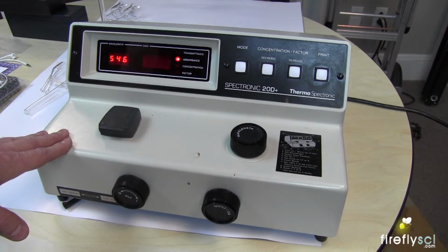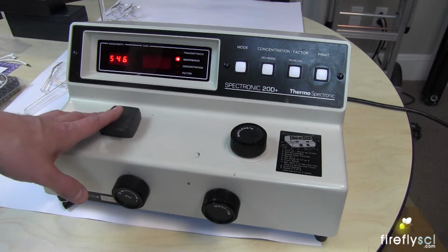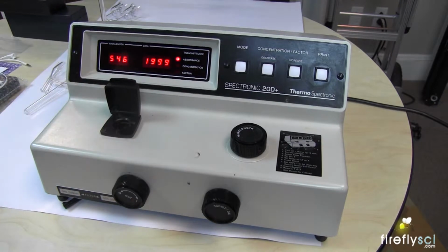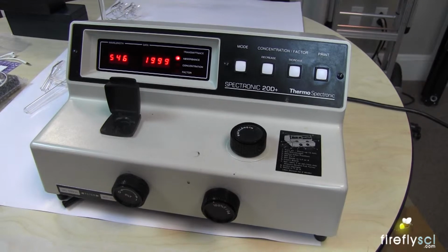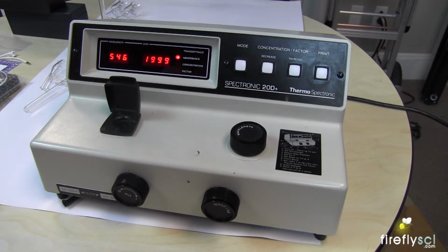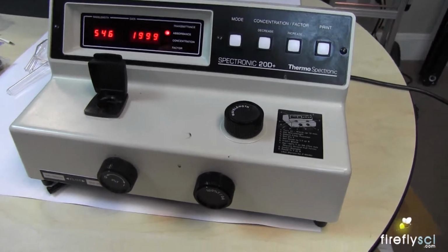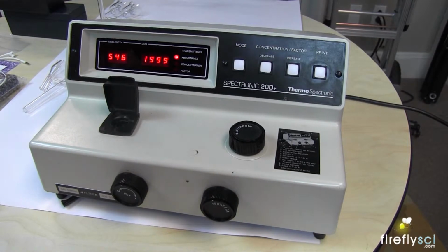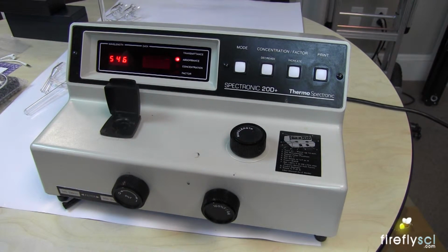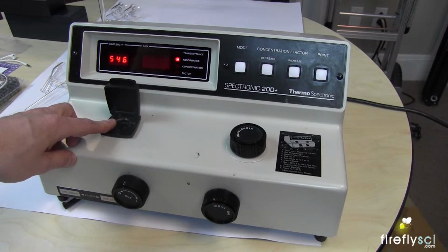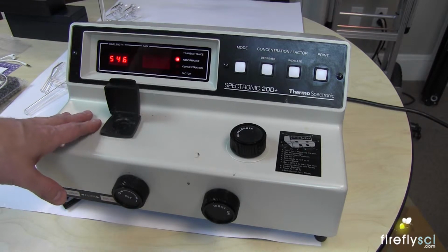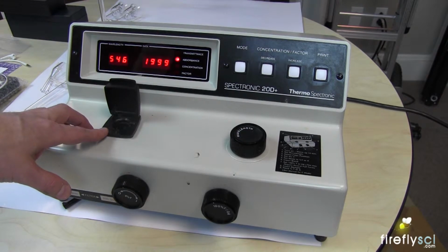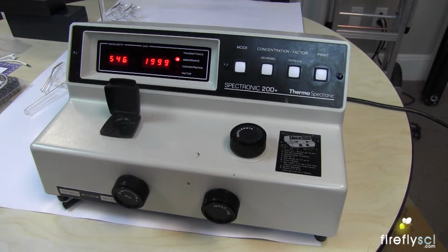Now, some interesting things about this machine. What I initially did was try to zero it with nothing in the cuvette holder. Let me take the camera off for a second so I can show you what we're working on. Inside here is where the cuvette goes. What I did initially was put our calibration standard into this holder, I pushed it down, and it fell into the machine because this is a very deep holder. This is not your standard size holder. Let me get one of the test tubes to show you what it looks like.